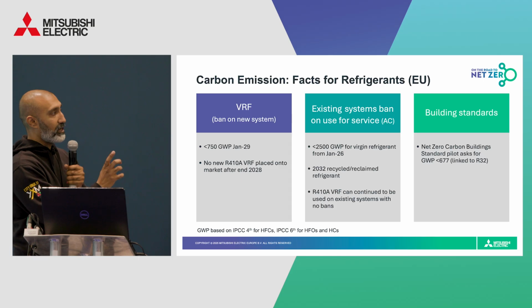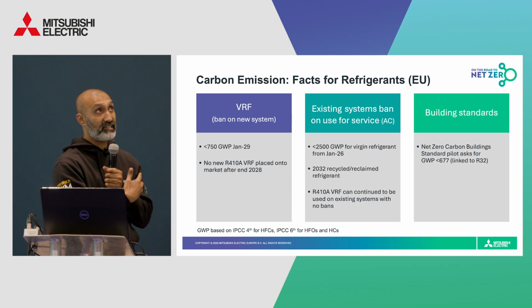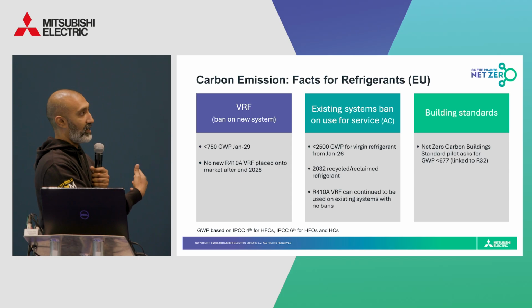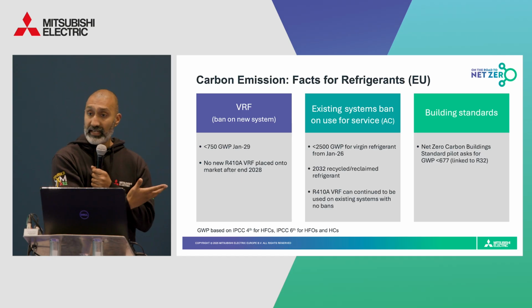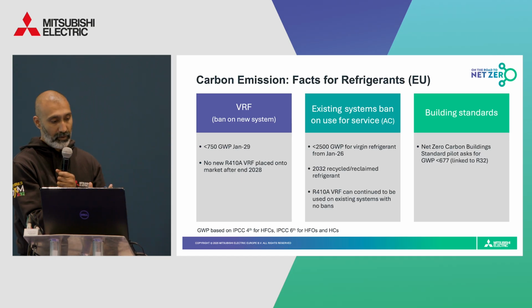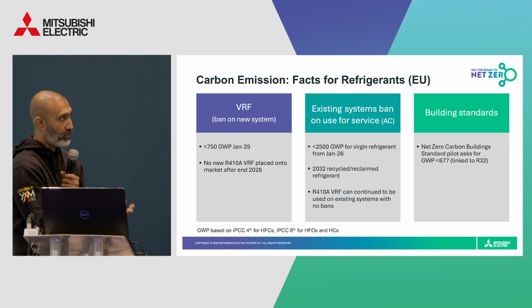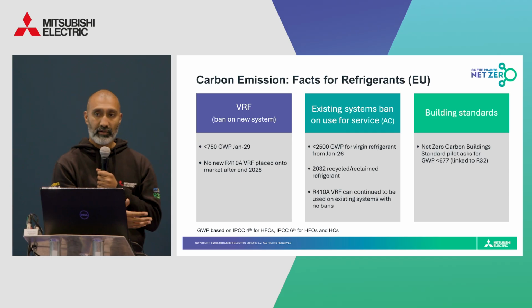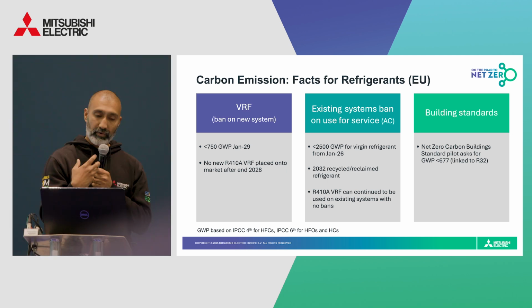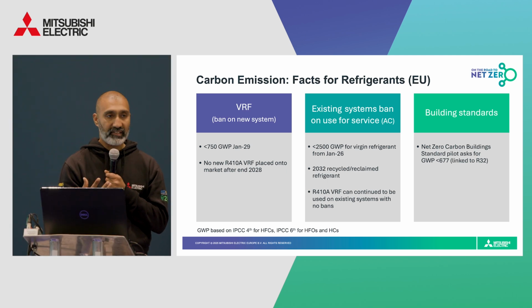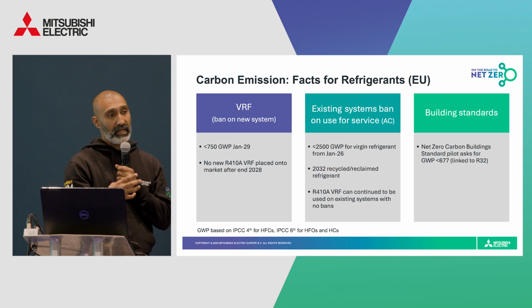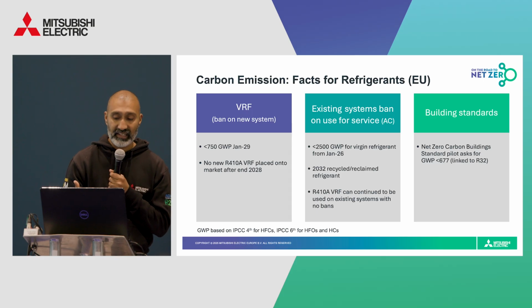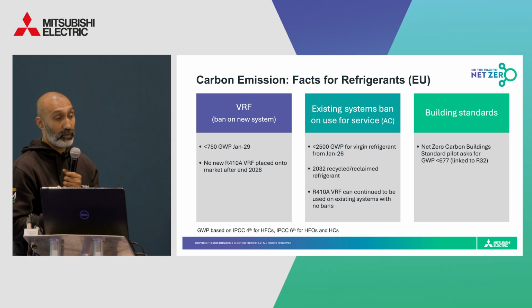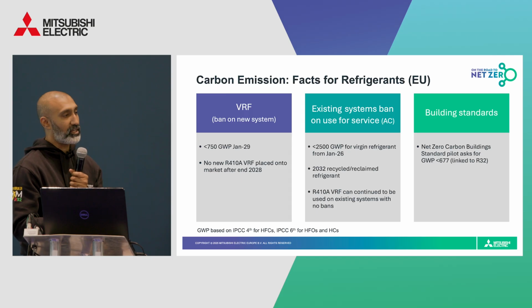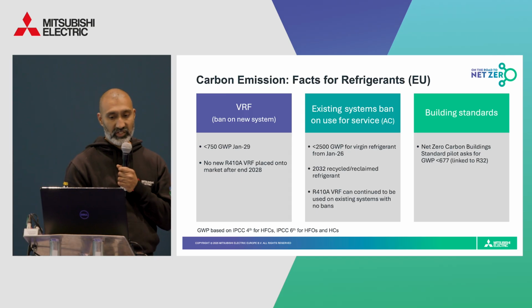Now, if you think about it, there is kind of a link between the sentiment behind the EU F-gas regulations and the UK Net Zero Carbon Building Standard, for instance. They both aim to phase down the use of high GWP refrigerants, and the UK Net Zero Carbon Building Standard actually reinforces this by saying that any refrigerants used in any in-scope refrigerant systems must meet a GWP threshold, and that threshold has been set at 677, which then puts R32-based systems as a really strong compliant choice for future-ready installations.